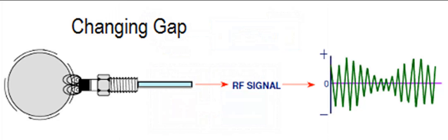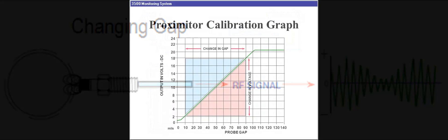Signal conditioning electronics amplify and filter the induced voltage, making it suitable for analysis. As the machinery operates, any vibration or movement causes changes in the distance between the probe tip and the surface. This change is detected as a variation in the induced voltage. Engineers analyze this voltage signal over time to understand the vibration characteristics of the machinery.